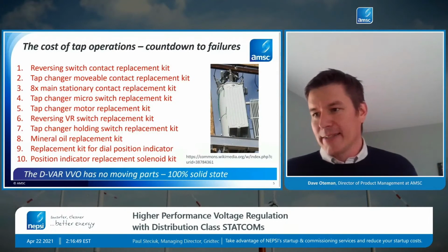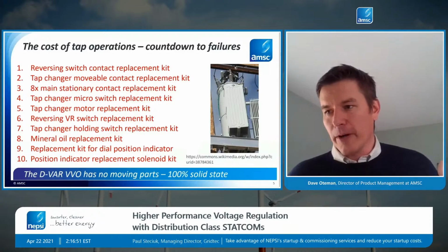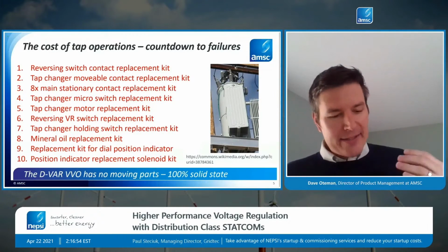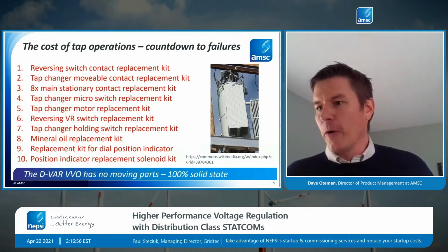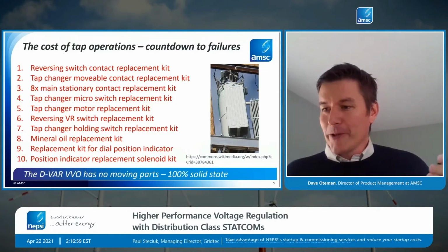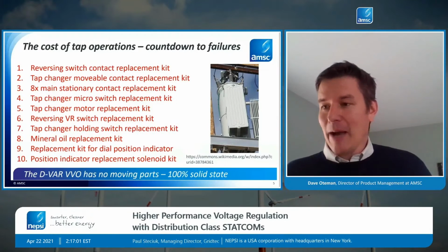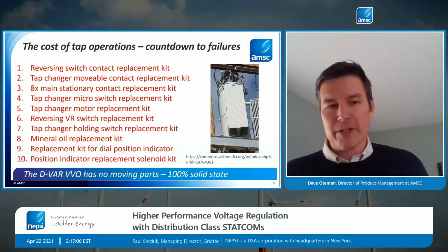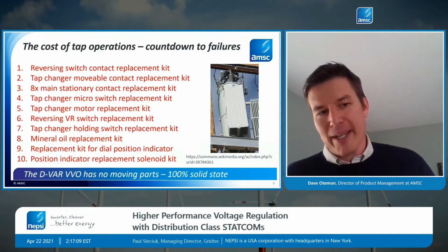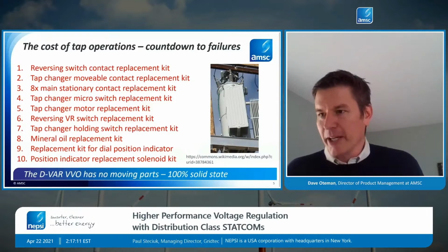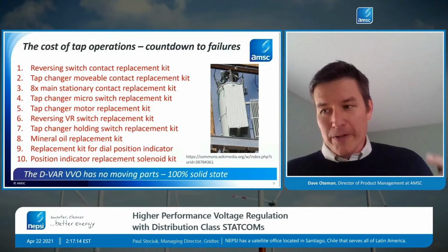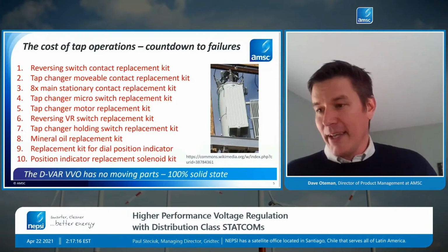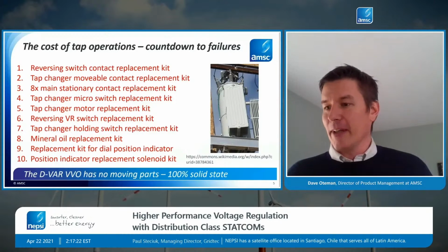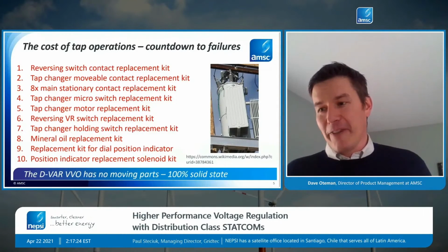I mentioned the limitations on tapping for a line regulator. That's driven by very real failure modes. As we see more solar feeders with very high adoptions of solar, this is becoming a serious problem also for line load tap changers. Here's a summary of all the mechanical failure modes in a tap changing regulator. I've got 10 listed here, and one of them has 8 separate components that can fail the same way. So there are actually 17 failure modes in a line regulator, and that's just a single phase regulator.